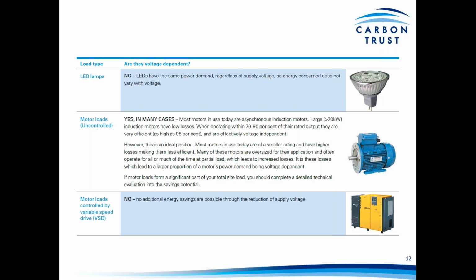Should also just point out that motor loads controlled by variable speed drives are not voltage dependent. So you don't have most of the inefficiencies there that we just described above. So there would be no additional savings possible through the reduction of the supply voltage here.